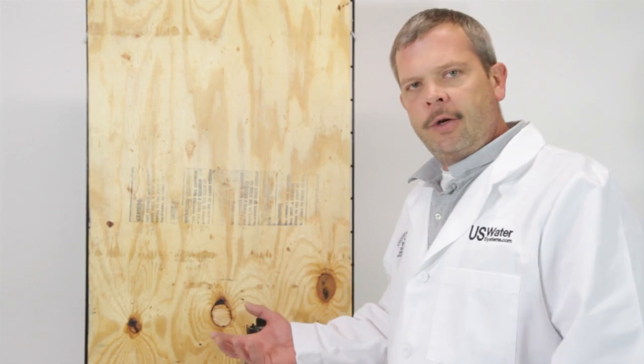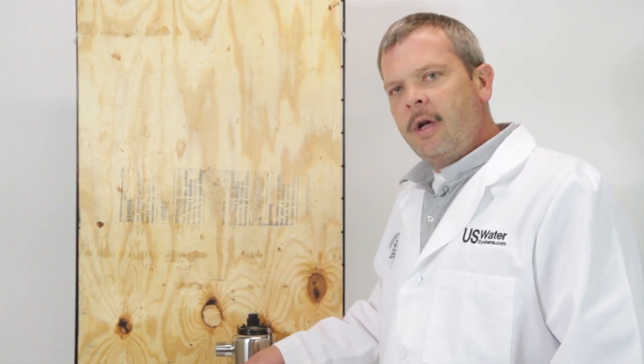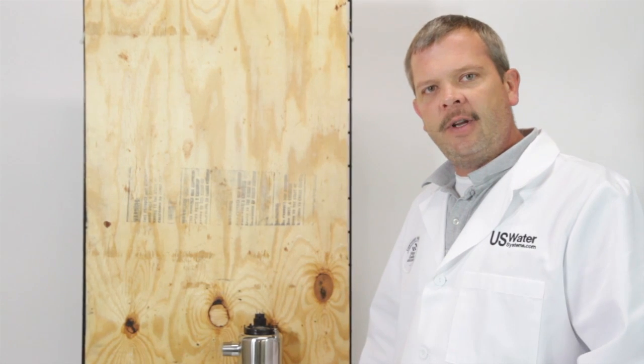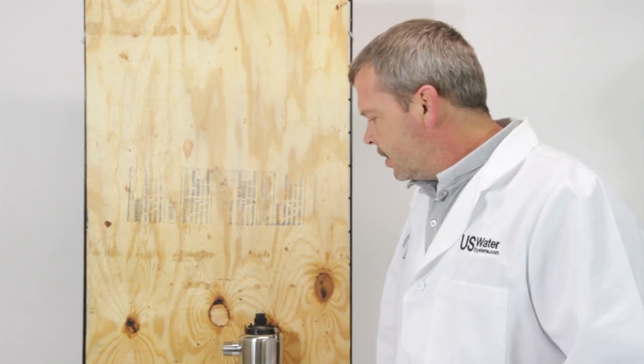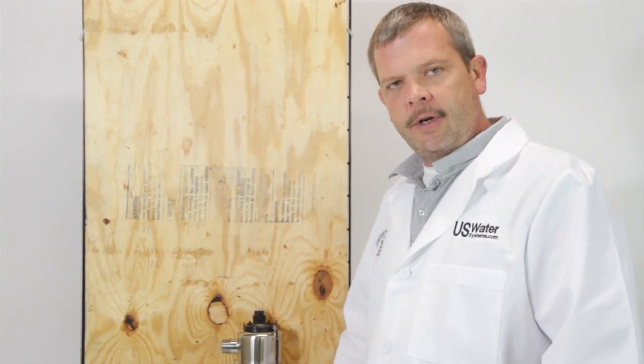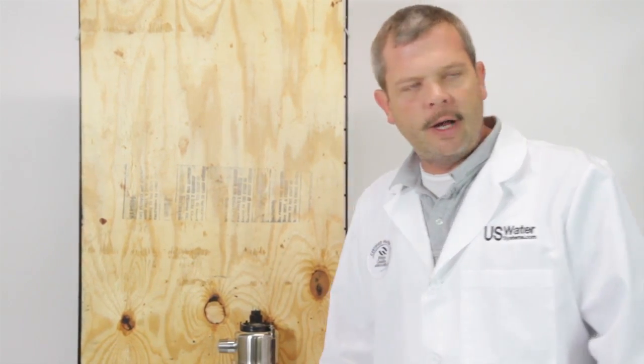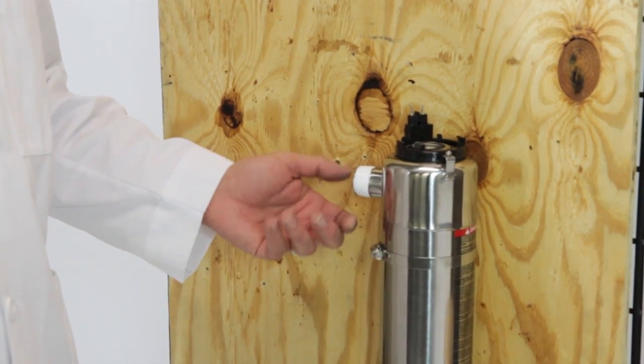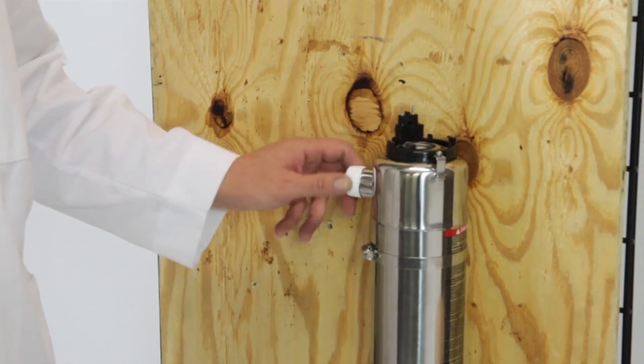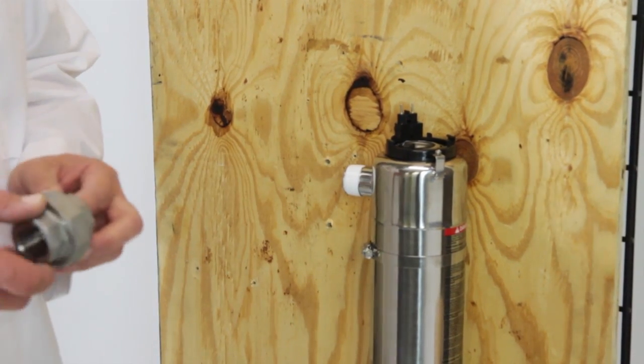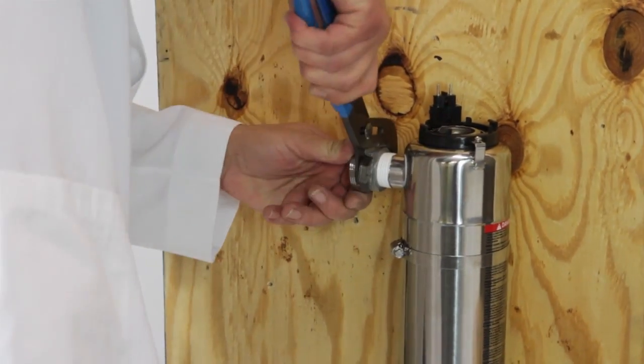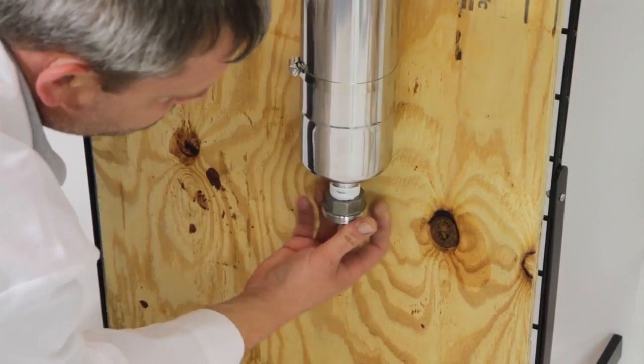Now we're going to use a standard stainless steel union. Normally we would bond the pipe between the top and the bottom, but because we are using plastic PEX pipe today, bonding isn't nearly as important. We're going to Teflon tape these and install our unions on the top and the bottom. Teflon tape these fittings before you mount the chamber or at least make sure that you have it loose so you can spin it around to get these ports Teflon taped. I always use the male side of the union and put it on the chamber.